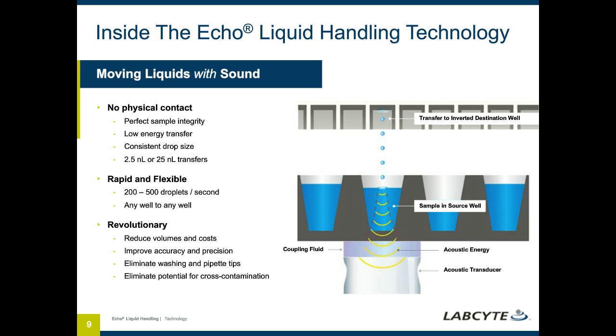So the gray area above the transducer is a depiction of that microtiter plate. We're showing 4 wells there. The liquid within those is at various heights. That's not a problem for the instrument. And then between the transducer and the bottom of the plate is a coupling fluid, and we simply use water for that. And that simply enables the acoustic energy to travel from the transducer into the plate.